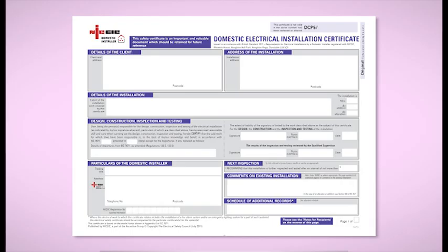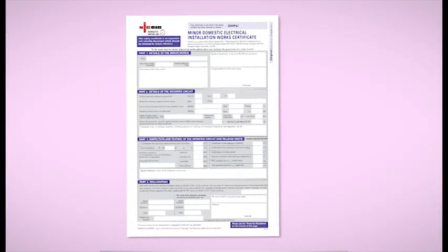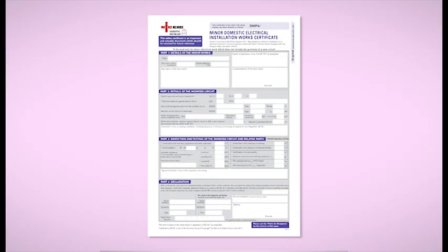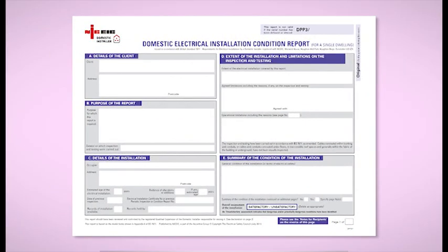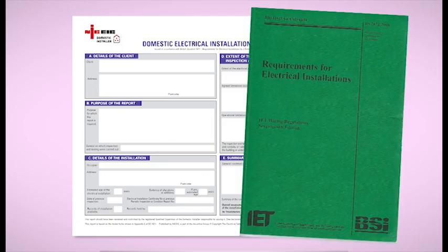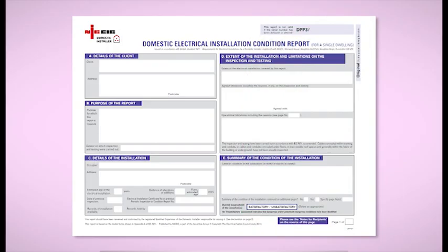Upon completion of a new installation or alterations or additions to an existing installation, the appropriate certification must be issued. For new installations, rewires, or the provision of any new circuit, this will be an electrical installation certificate. For an alteration or addition to an existing circuit, it will be a minor electrical installation work certificate. For reporting on the condition of an existing installation, an electrical installation condition report must be used. This was a major change introduced with Amendment No. 1 of the 17th edition and replaced the periodic inspection report as the form to be used for periodic inspection and testing.